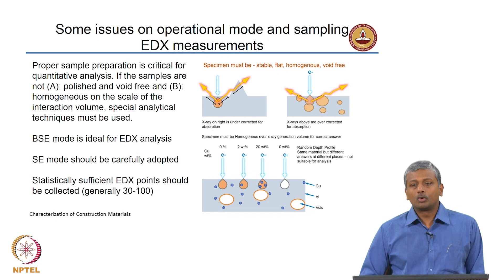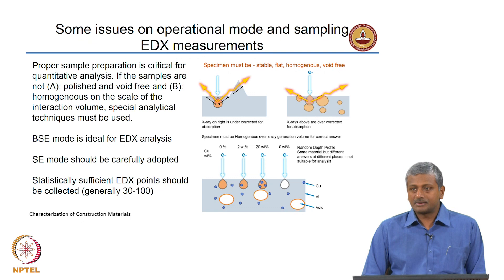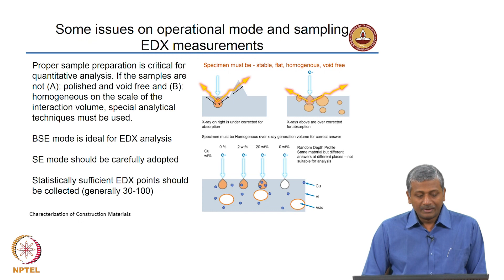Now there are certain rules to be followed when doing measurements with EDX. It is not very simple to get EDX counts or X-ray counts when you do the analysis or the microscopy itself. First of all, proper specimen preparation is important. If the samples are not polished, not void-free, and not homogeneous on the scale of the interaction volume, you can get a lot of errors.